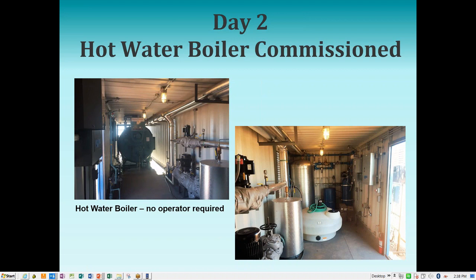You can see the left side of the container, of course that's the boiler. Over to the right is the water treating equipment, and there's a small water makeup tank there. I want to pause here and say the boiler is in a closed loop. It's a hot water boiler, not a steam boiler, so we don't have to have on-site trained personnel and permits. It's basically like the hot water heater in your house. There's really no need for makeup water, we've got that there in case of an emergency where we need to add water to the boiler. So it's in a closed loop, and as John said, the ORC is in a closed loop as well.